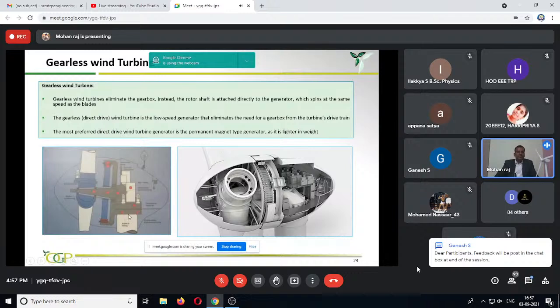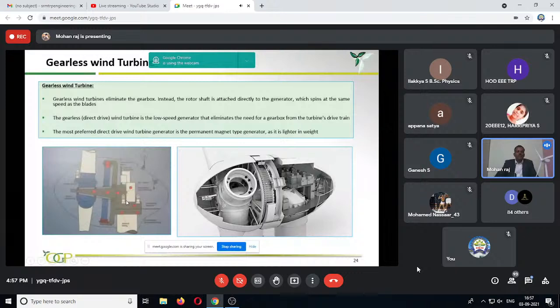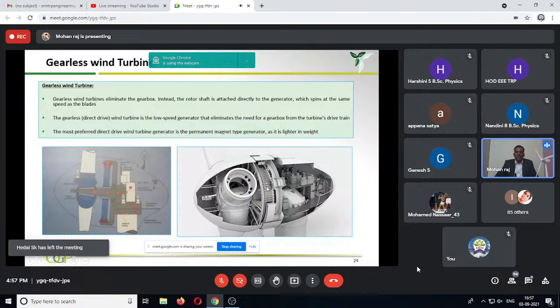And this is called the yawing operation. These two motors are called the yaw motors, which can align the turbine to the wind direction. The yaw motor will rotate the yaw bearing, and based on the wind vane signal, it will operate. You see the cross section of the wind turbine. This is the rotor, and this is the hub, which is mounted. Blades are mounted in this hub, and this is the excited rotor. Actually, this manufacturer is using excited rotors, and the field windings are available in the rotor. And this is the stator winding.